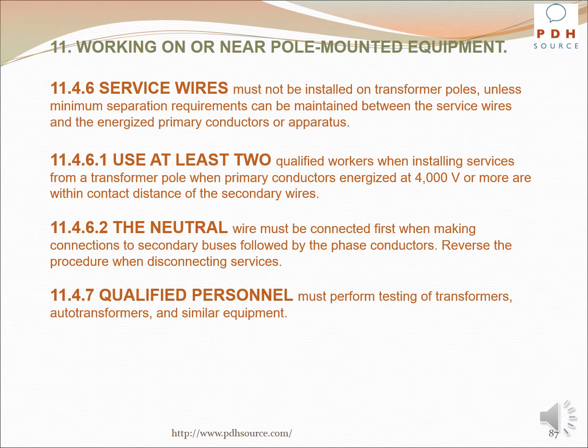Service wires must not be installed on transformer poles unless minimum separation requirements can be maintained between the service wires and the energized primary conductors or apparatus. Use at least 2 qualified workers when installing services from a transformer pole when primary conductors energized at 4,000 volts or more are within contact distance of the secondary wires. The neutral wire must be connected first when making connections to secondary buses, followed by the phase conductors. Reverse the procedure when disconnecting services.